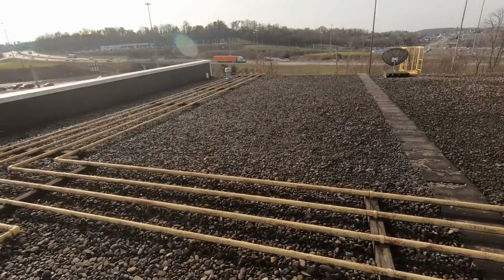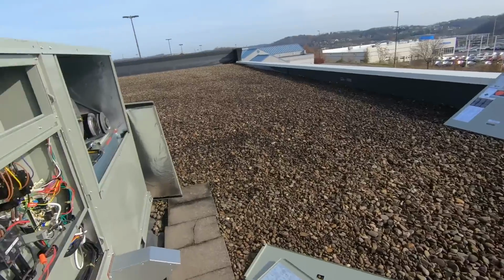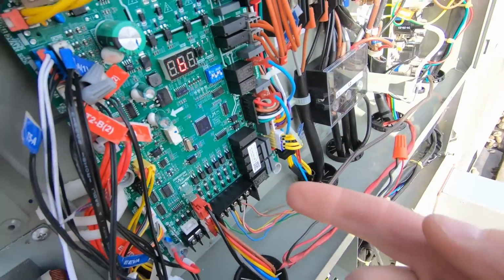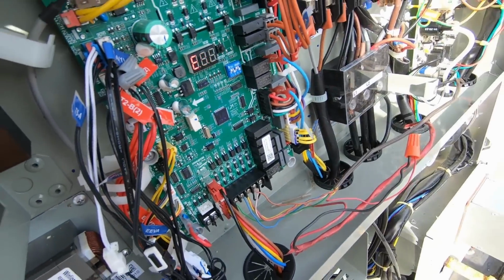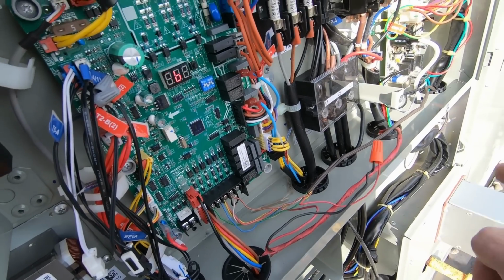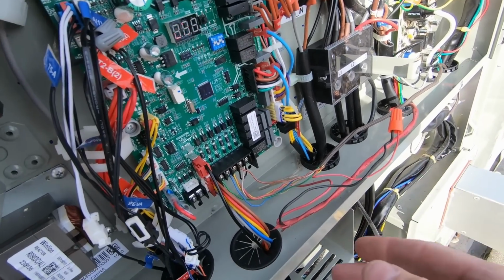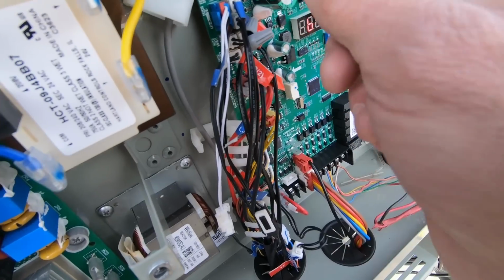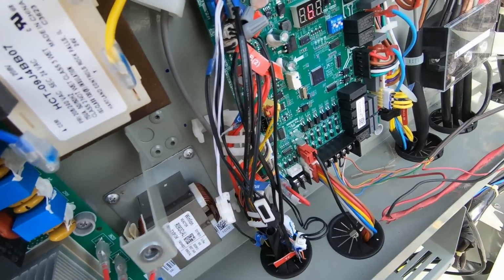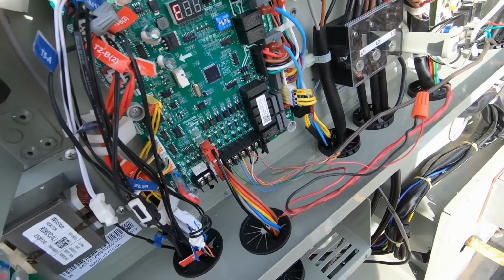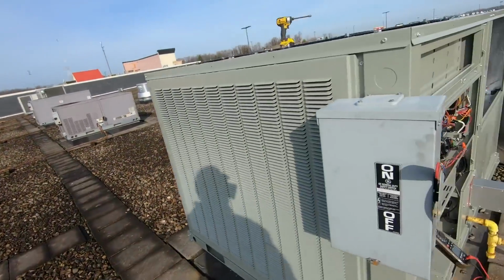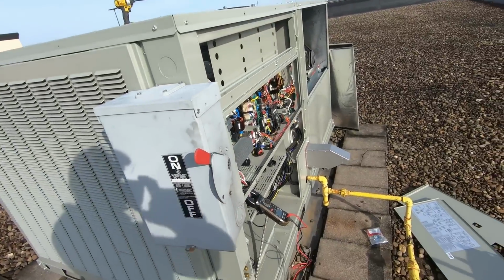I think we're going to end up resetting this system, because I don't have 24 volts coming out of the board to do any control - not through the smoke detector, not through the thermostat, nowhere. But I do have 24 volts here coming off the transformer directly to our board, so it's probably just locked out. I'll be back with at least 2 zip ties.